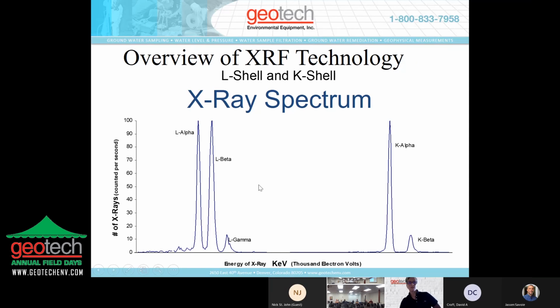So once again, depending on what looks better for each sample, you can calibrate it. If you're trying to calibrate an instrument for various elements and you have a little bit of coelution, where your peaks are kind of mixed together, you can choose to calibrate it off the K alpha, either the K lines or the L lines. Most soil samples are K lines until you start to get to things like gold, lead, and tungsten.